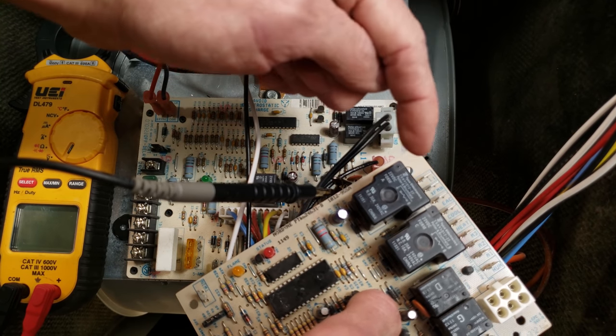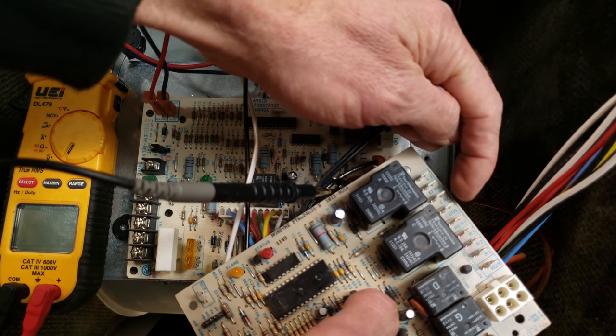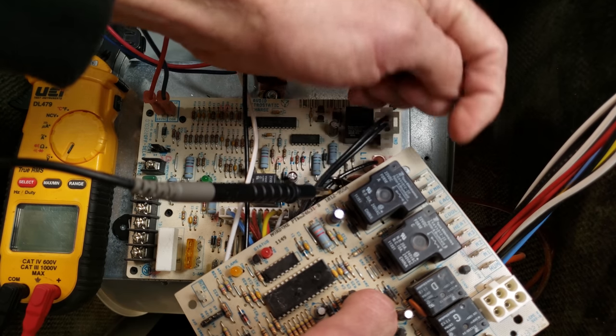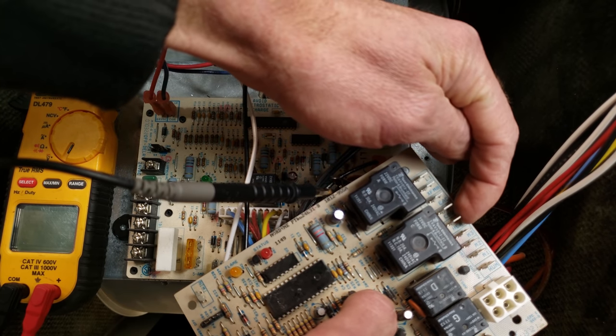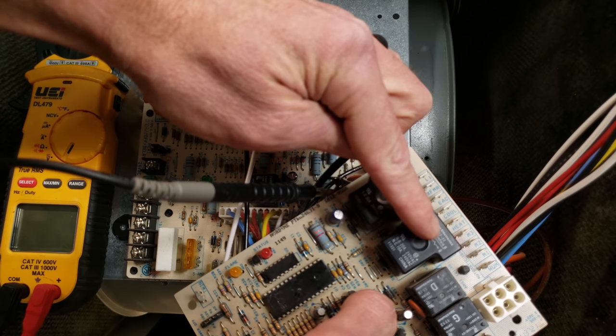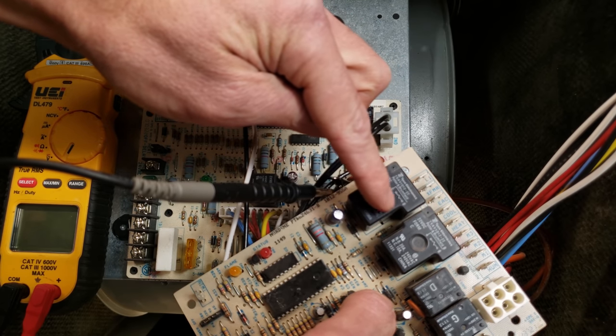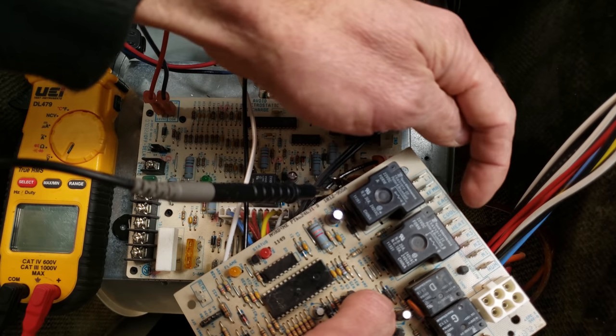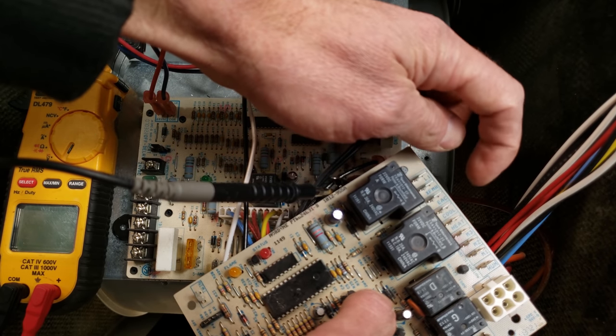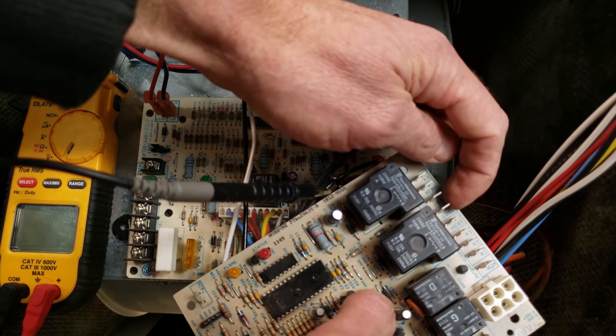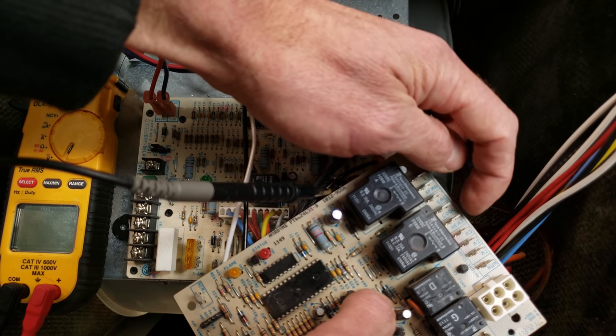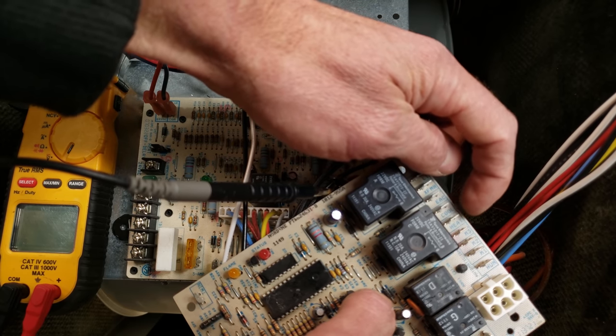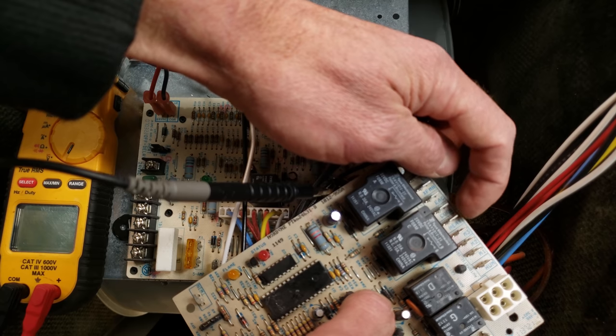You can check some of these with resistance and a lot of these control boards have an enclosed relay like this right here, here's another example right here and here's yet another one. So you're really looking for a voltage drop between L1 and your cooling tap or L1 and your heating tap in order to see if you have a high resistance across the contacts. I also want to point out that your heat speed is usually used for your fan, cooling speed is usually used for air conditioning mode, and this heat terminal is not going to have power on it in heating mode until the full sequence of operation for heat is complete and the heat exchanger is warmed up.